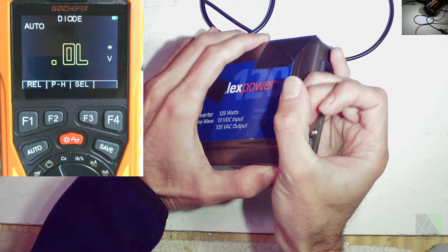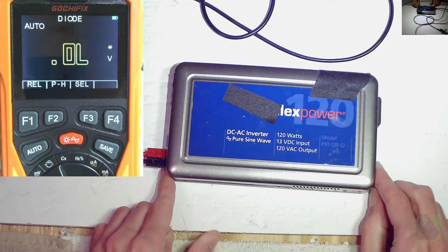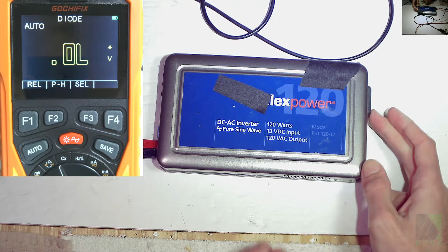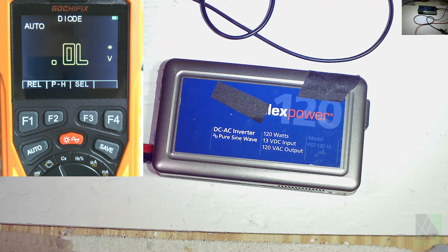The most basic check would be to see if the inverter is on, and this inverter is on. It's hard to see, but the power light is on. It's putting out AC power. So the first thing I'd like to see is, what is the output at the terminals? That plug is actually right here on the side. Is it actually putting out 120 volts AC?